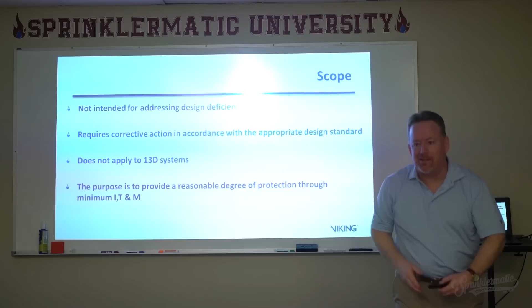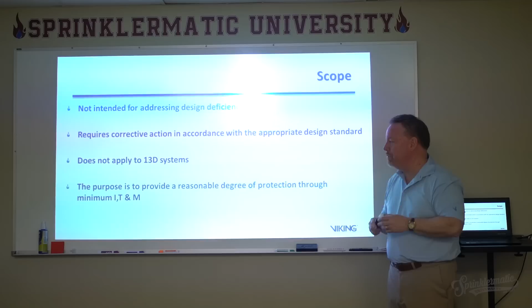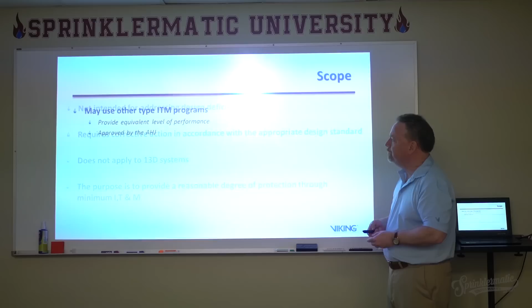So the document says a reasonable degree and then says, you guys go figure that out. We're going to work on it from here as far as frequencies of some of these, but in some of the other cases, you're just going to need to discuss what that is. You can use other types of ITM programs and different frequencies. Frequencies can change from what NFPA 25 is establishing, but it needs the approval of the authority having jurisdiction in order to do so. Remember, 25 is the law, so any modifications of the law are always going to need the AHJ's approval.